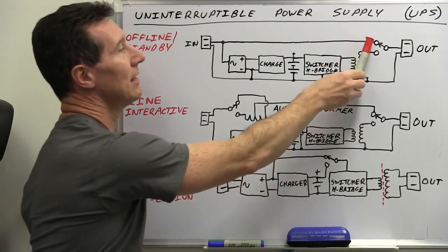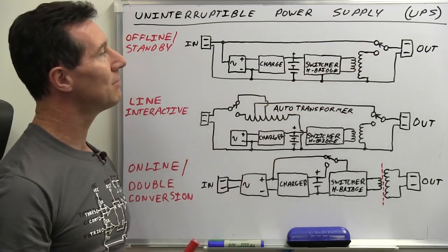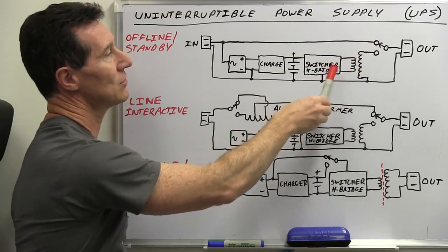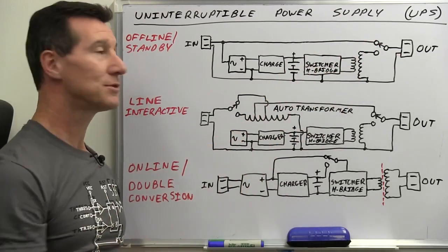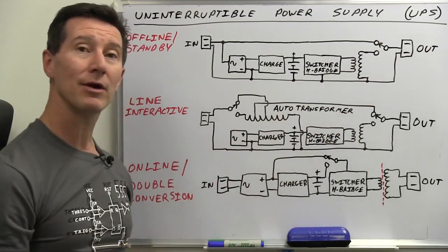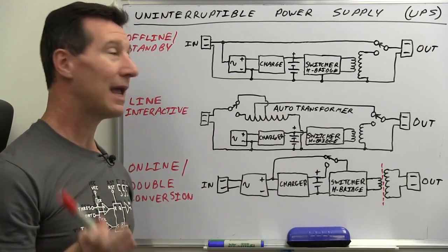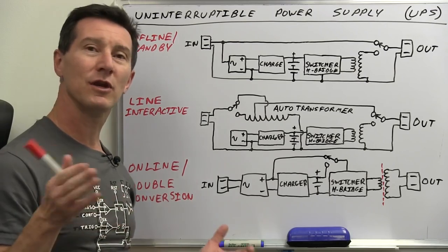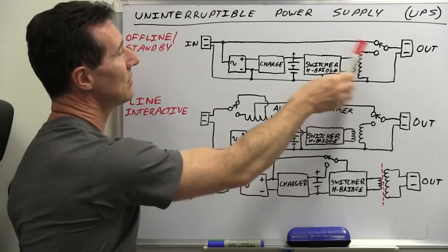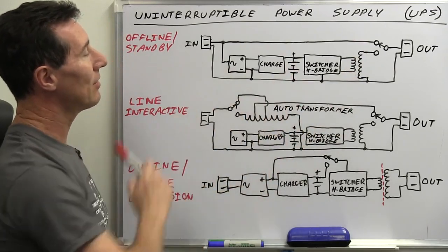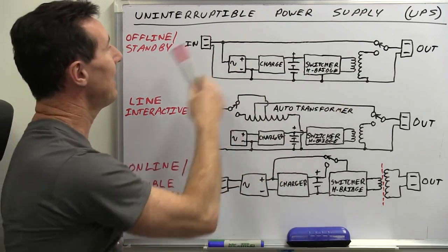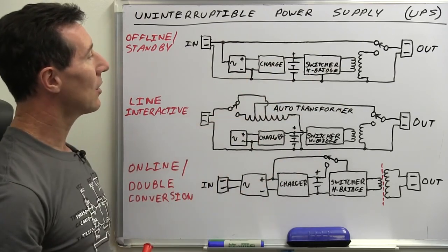It can usually take tens of milliseconds, or 100 milliseconds or so, to switch over and start up. So the device you're actually powering has to be able to handle that little dropout or brownout as it switches over to battery backup. Now that's the cheapest and most common one.